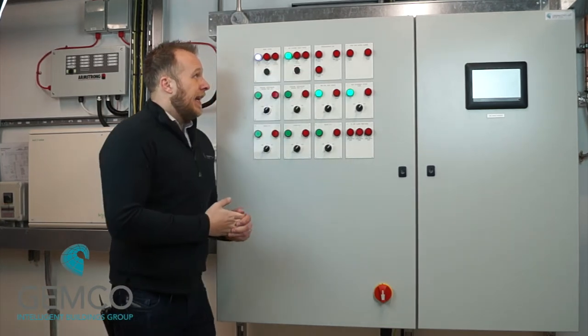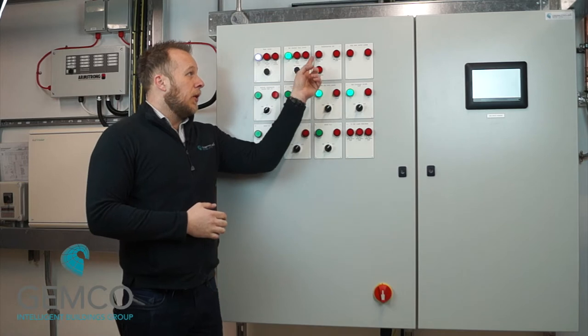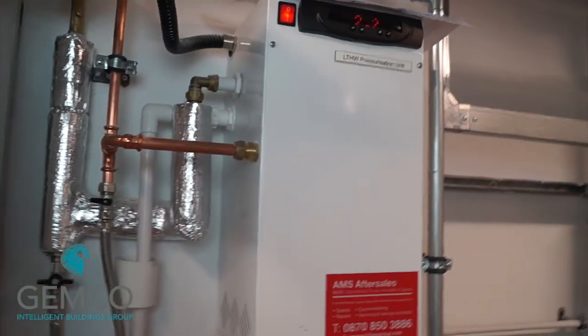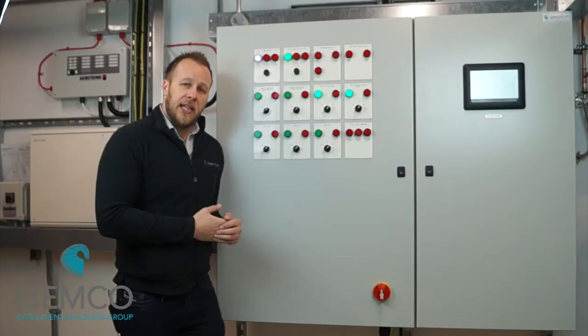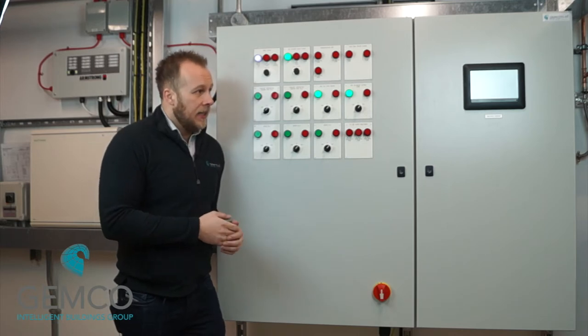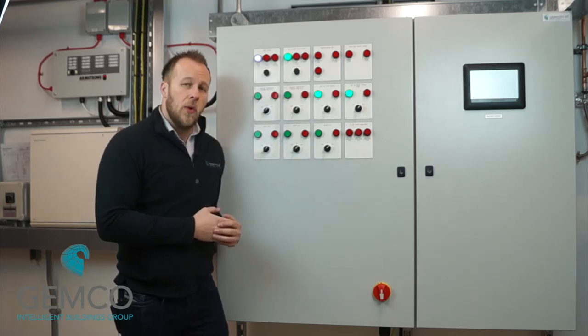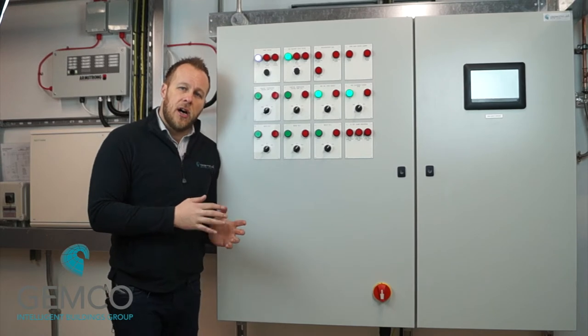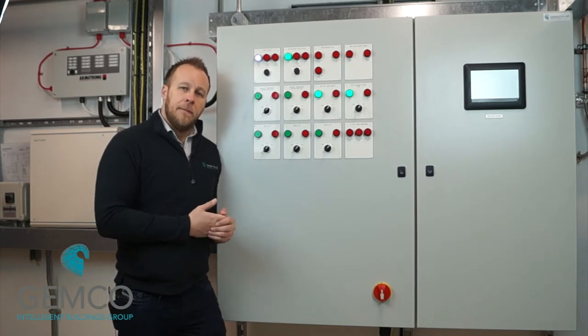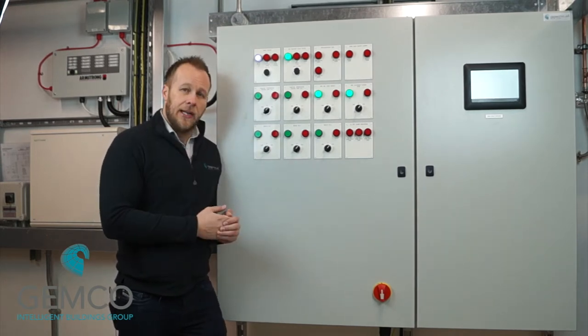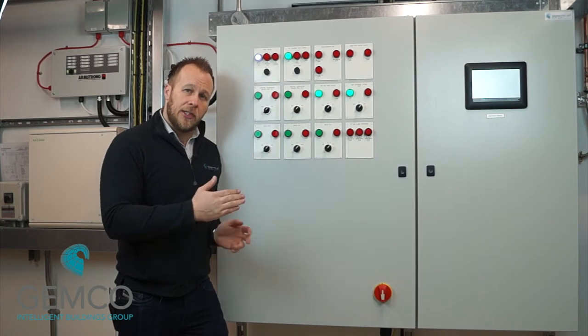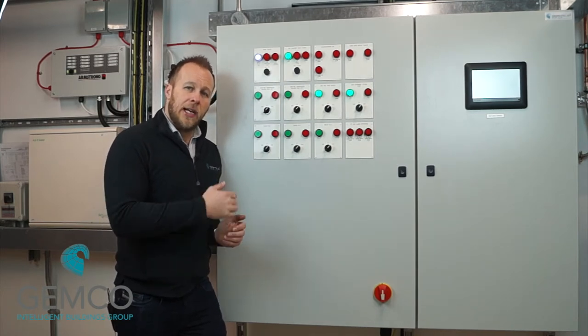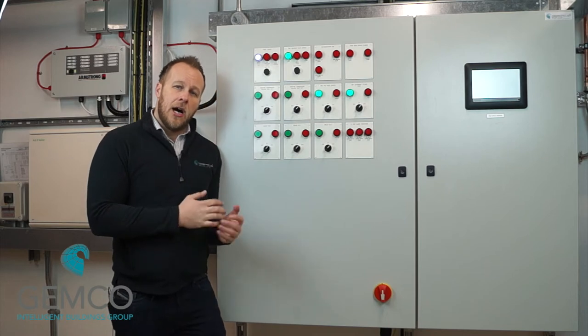Moving on from that, there is another label which monitors the pressurization unit. Now the pressurization unit is another safety circuit. It's a hardwired safety circuit. There's a pressurization unit over on the wall there, and what we do is we monitor the high and low levels of pressure determined by that unit. Now if the system goes high pressure or low pressure, then we're going to momentarily hold the pumps off.